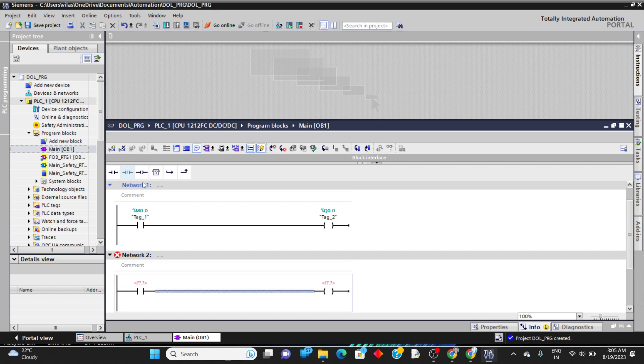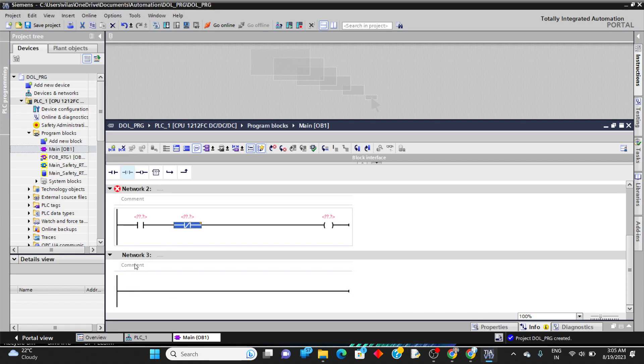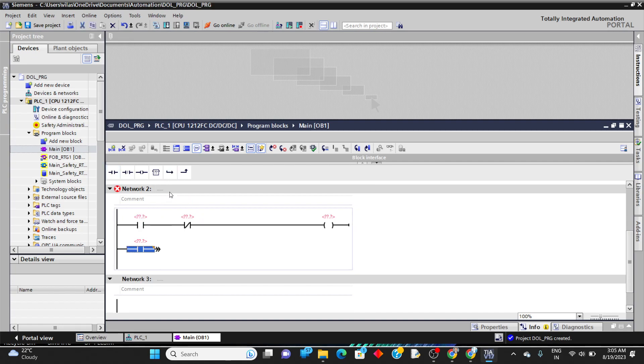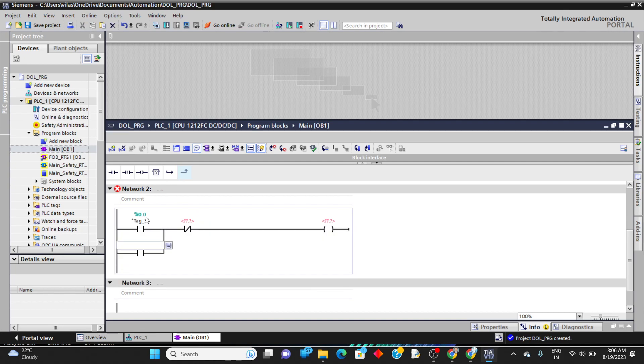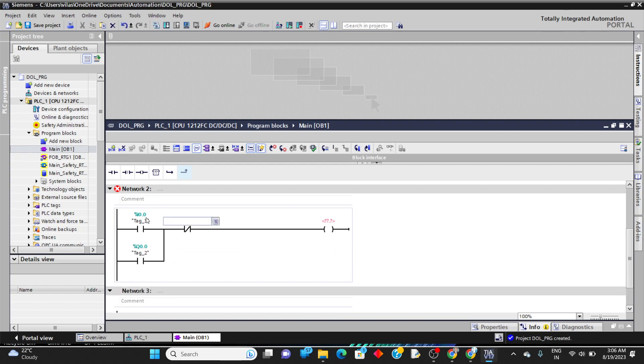Take a normally open and normally closed contact, and add a parallel contact. To add a parallel contact to the normally open contact, select the rail and click on open branch — one branch will open. Click on the NO contact and connect it. I'll assign I 0.0, then Q 0.0 as the output, I 0.1 as another input. We have to use the same addresses as mentioned on the PLC.